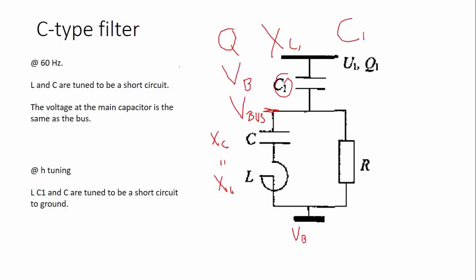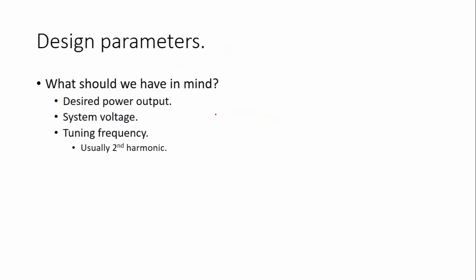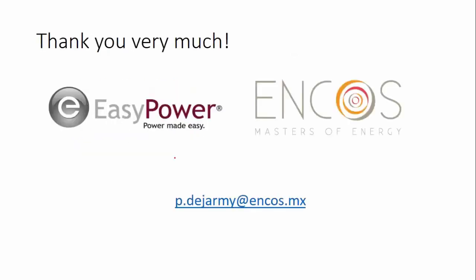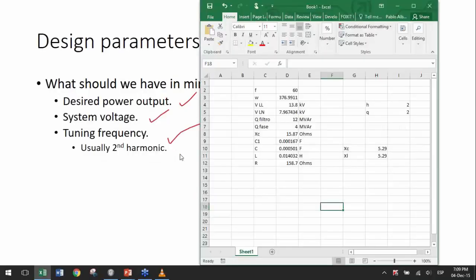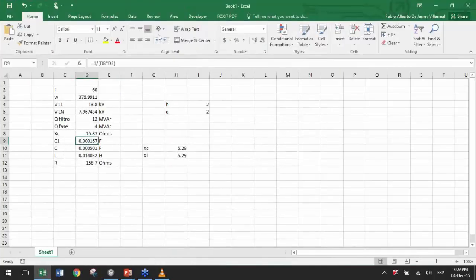Now, through some circuit analysis, which I will not perform here, we can arrive at some equations which are very, very simple. And we should only have in mind how much power we need from that filter, what the system voltage is, and what the tuning frequency will be. Usually, this type of filter is used for the second harmonic. It's the most widespread use I've seen. There are some very easy formulas for C1. This is the main power capacitor. For C, let's say CS, it's the series branch, and the LS. These are some very, very simple formulas that can be programmed in an Excel.